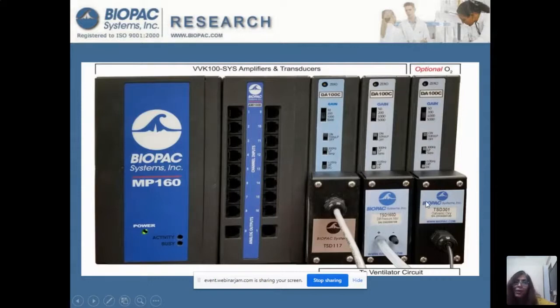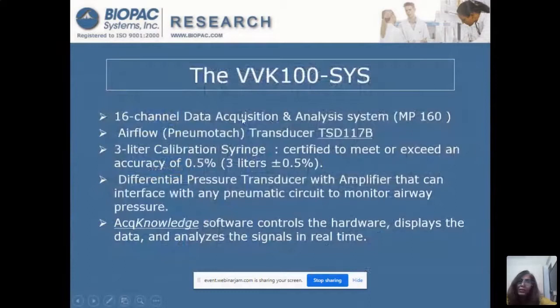This is the basic system and how it looks. You have the data acquisition, and you only need an airflow transducer and a differential pressure transducer to validate the ventilator. The basic system has a 16-channel data acquisition system and a calibration syringe to monitor the volume, with accuracy of 0.5%. The differential pressure transducer can be connected to any pneumatic circuit to monitor airway pressure, with AcqKnowledge software to analyze and display the data in real time.